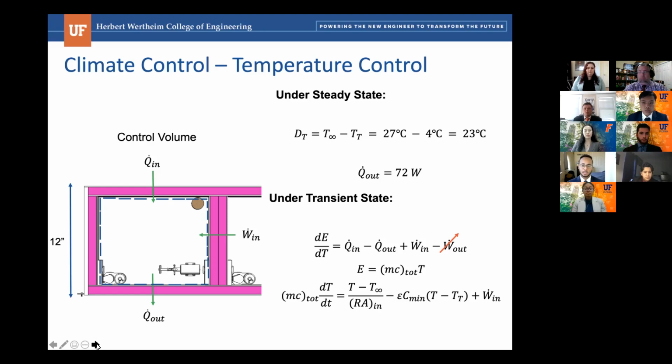And so we have heat coming in from outside of the casing, as well as heat coming in from the different electrical devices and other devices inside the system, involving the plate shakers as well as the optical measuring devices.